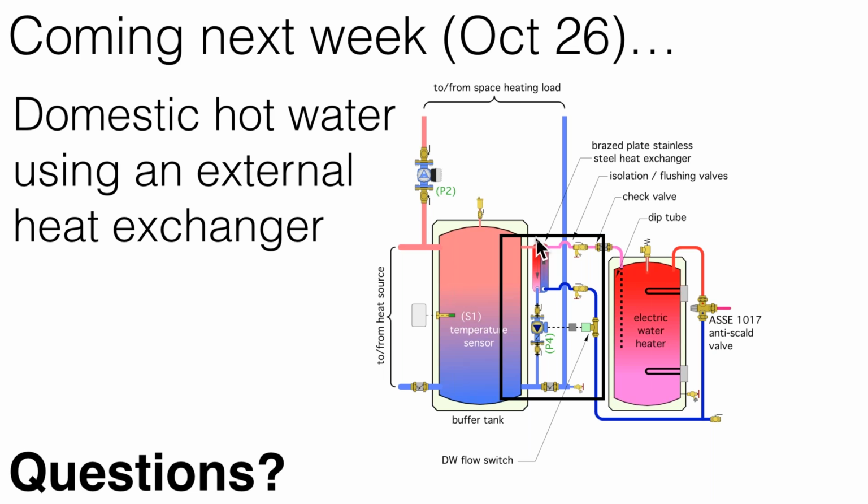So it's continuous circulation during the heating mode. And if all the thermostatic valves are closed, and if the thermostat that controls the great room is closed, in other words, if there's no open flow path, the pump will go down to what I call a sleep mode at about 9 watts. And it'll just sit there and wait for something to open up. It would be very similar to the small Velo, I think the EcoStratus Velo pump. Set it up for constant differential pressure mode, and it's enabled 24 hours a day.